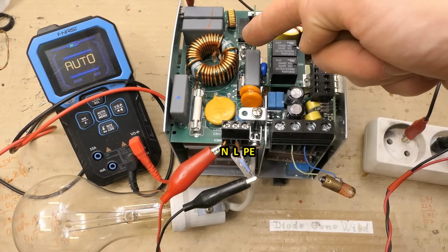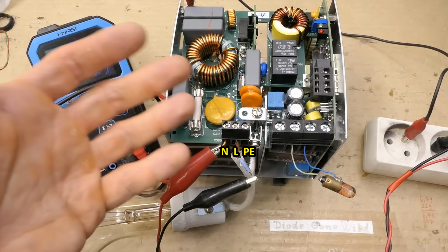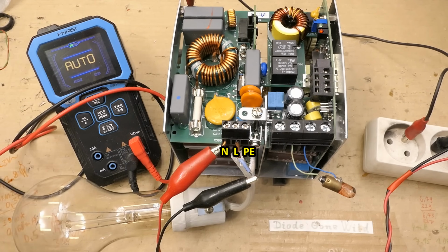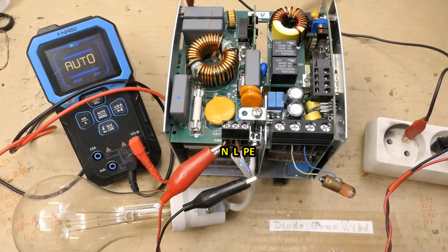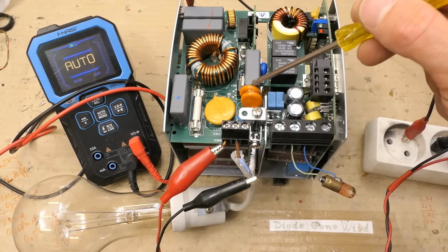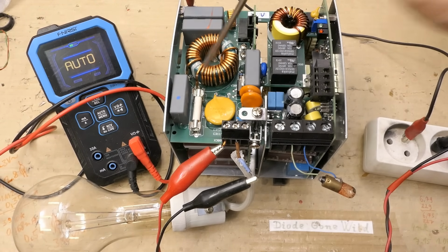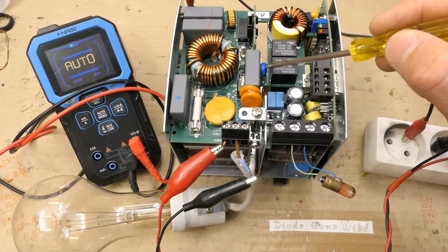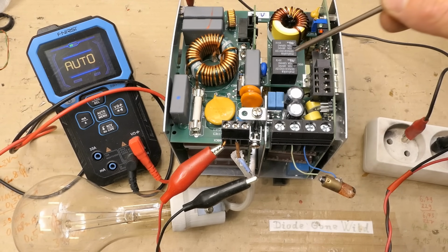Maybe these terminals arcing actually blew apart some soft start circuitry, because I don't see any NTC thermistor, which would also probably not be suitable for a 1 kilowatt power supply with high efficiency. These are marked as capacitor, these are not NTC, this is a metal oxide resistor, and this is marked as F, like fuse. What also baffles me is these relays.